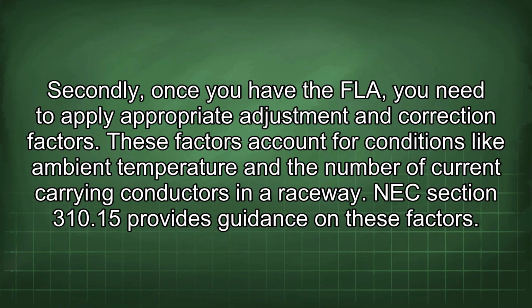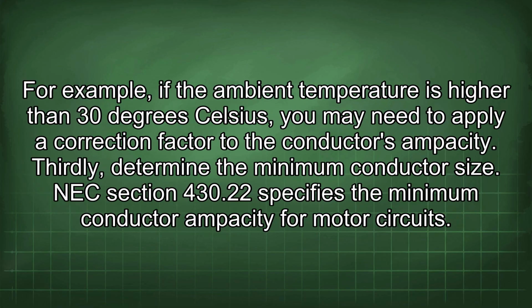Secondly, once you have the FLA, you need to apply appropriate adjustment and correction factors. These factors account for conditions like ambient temperature and the number of current-carrying conductors in a raceway. NEC Section 310.15 provides guidance on these factors. For example, if the ambient temperature is higher than 30 degrees Celsius, you may need to apply a correction factor to the conductor's ampacity. Thirdly, determine the minimum conductor size.